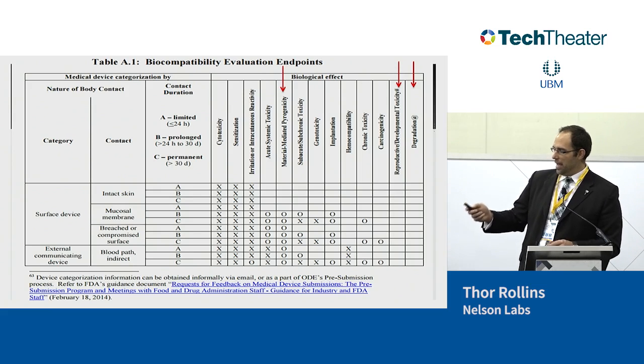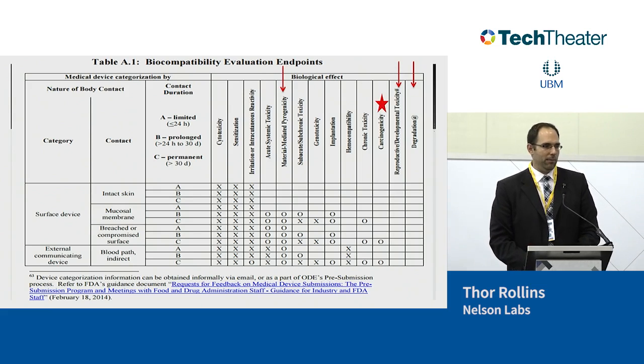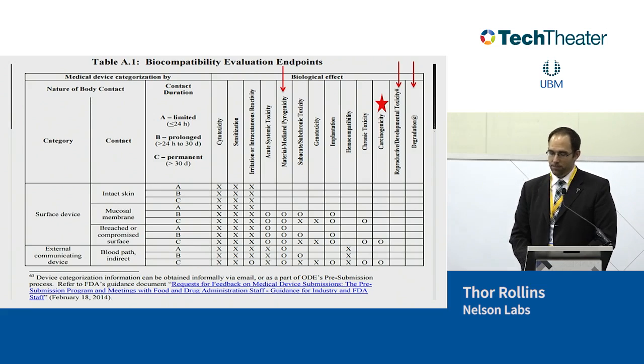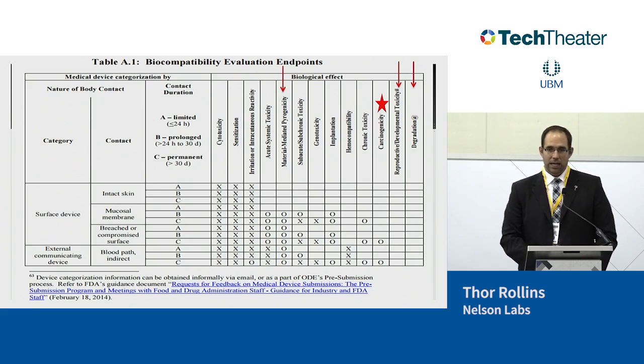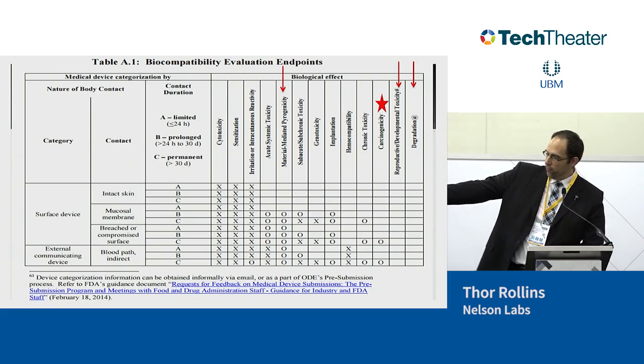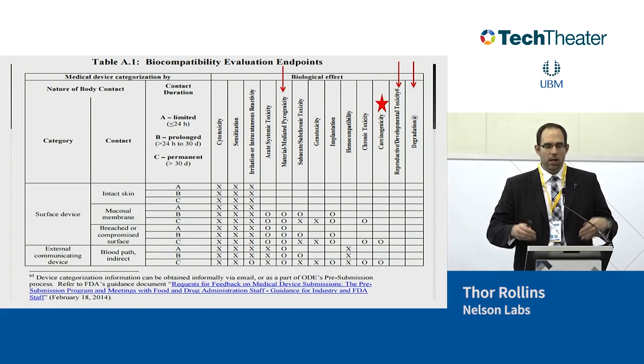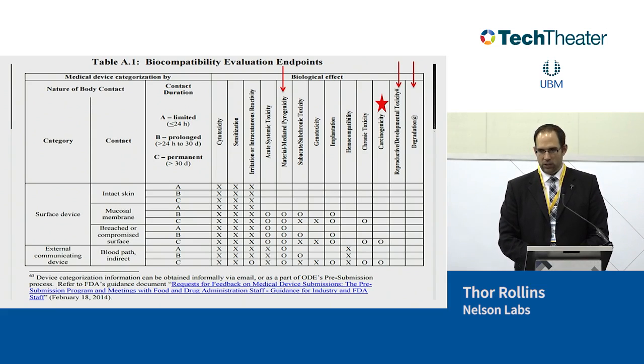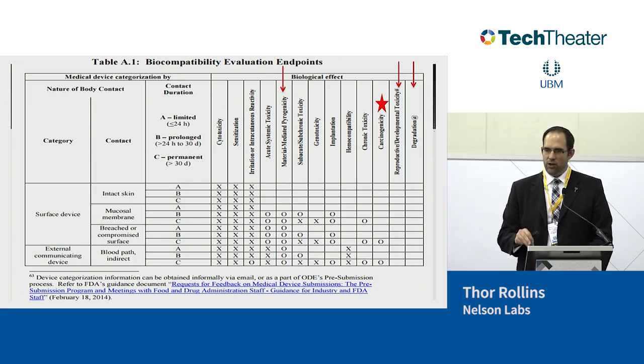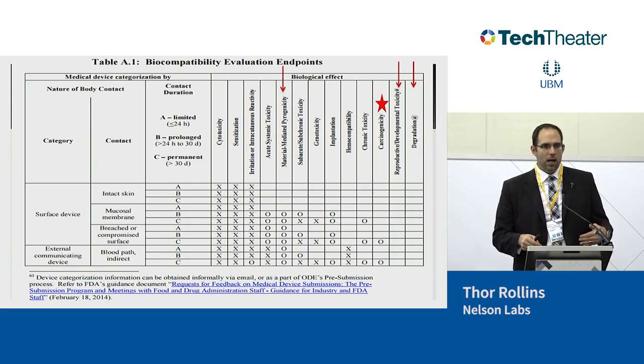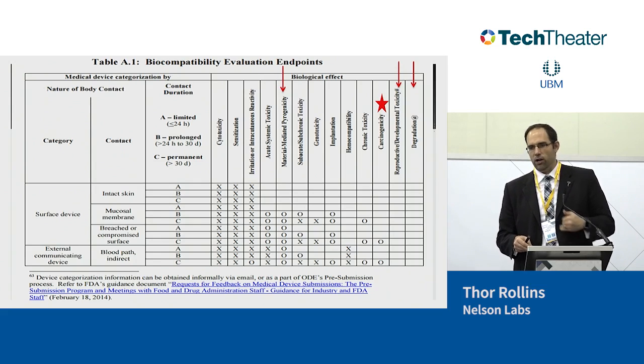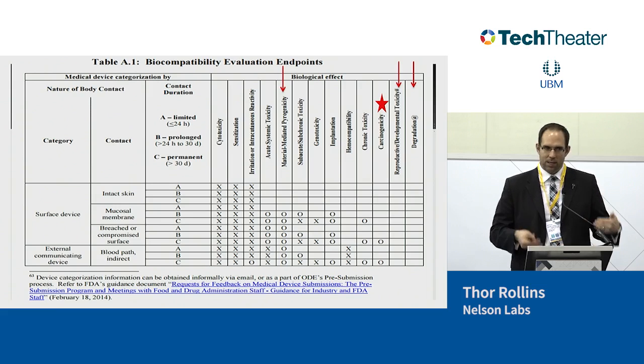But material-mediated pyrogen. And then the big one, carcinogenicity. Like I said, before this category was almost forgotten. Now the FDA is requiring us to assess that if it's an X or an O in that box. The other thing I want to mention is the new -1 that's coming out is also changing this chart a little bit. Before cytotoxicity, they're adding another column for material/chemical characterization. And every single thing is marked. When you see that, I don't want you to freak out that you think you have to do chemistry on every single device. But you do have to understand what your materials and your processes are for every single device. It's part of that risk assessment.